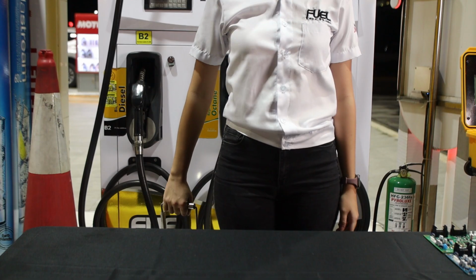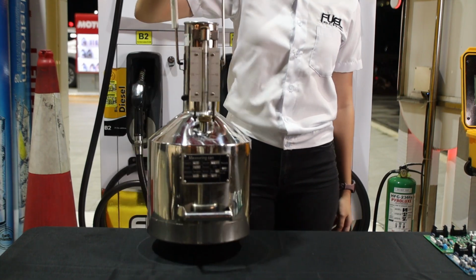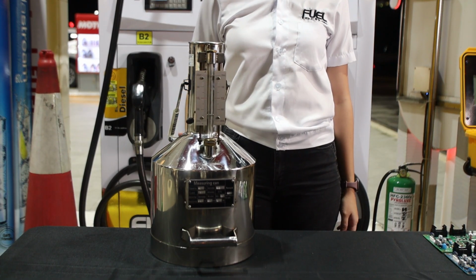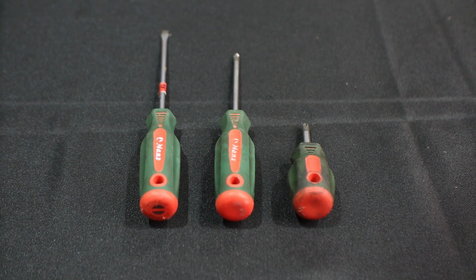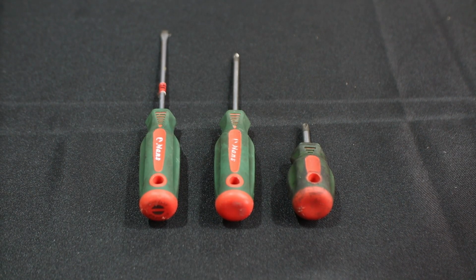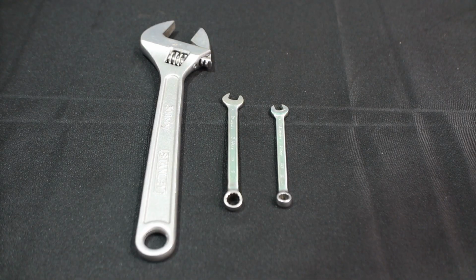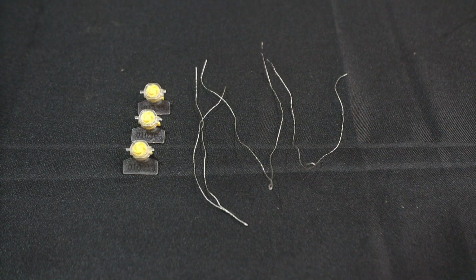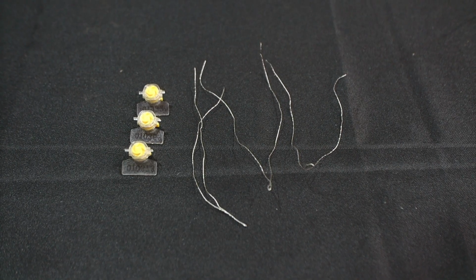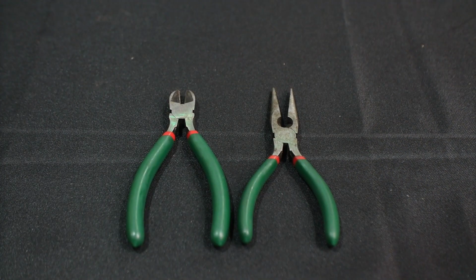Preparation, tools needed. Calibration test measure, typically a 10-liter container certified for accuracy. Screwdriver to access the calibration mechanism and make adjustments. Wrench for loosening or tightening any necessary bolts, screws, or seal wire. Seal wire used to reseal the calibration mechanism after adjustments. Long nose pliers for cutting and securing the seal wire.